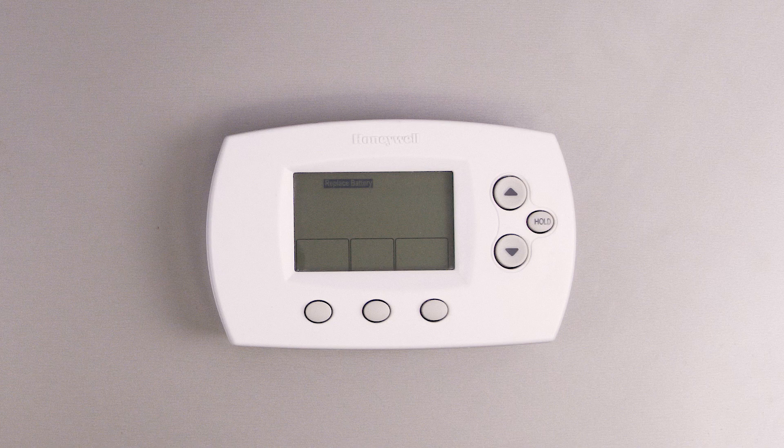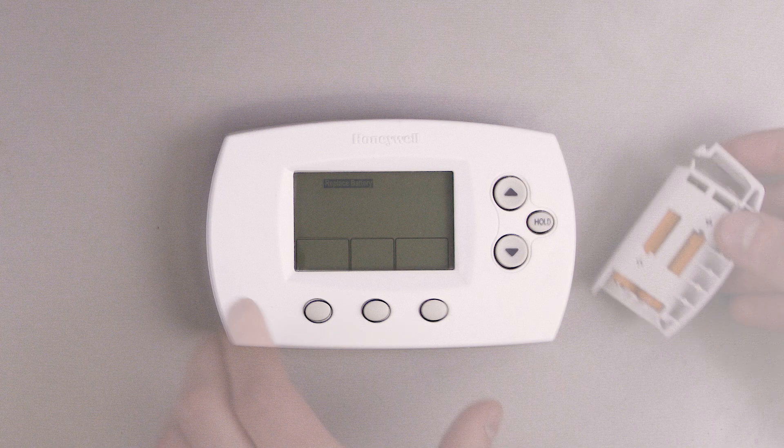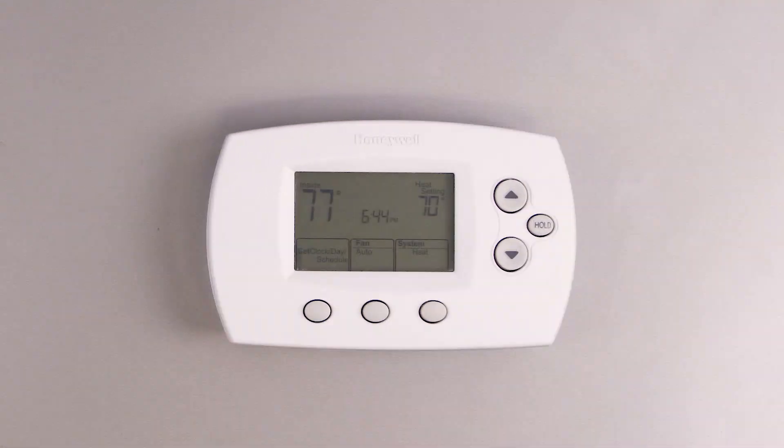If your furnace isn't running at all, it's best to eliminate the simple solutions first. Take a look at your thermostat. Check the batteries and replace them if necessary. Make sure that the thermostat is set to heat and the fan is set to auto.